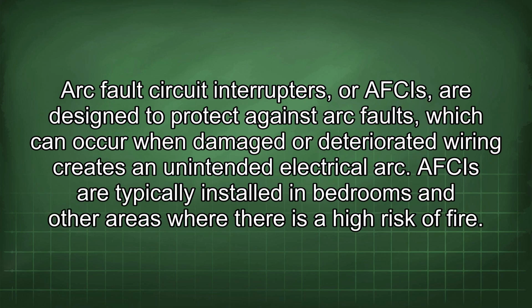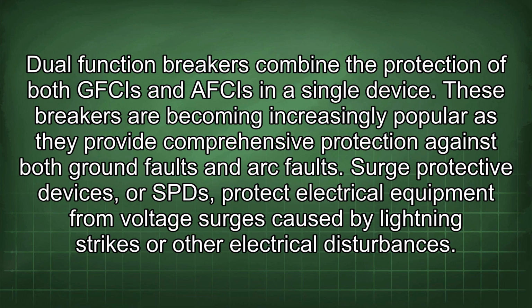Arc fault circuit interrupters, or AFCIs, are designed to protect against arc faults, which can occur when damaged or deteriorated wiring creates an unintended electrical arc. AFCIs are typically installed in bedrooms and other areas where there is a high risk of fire. Dual-function breakers combine the protection of both GFCIs and AFCIs in a single device. These breakers are becoming increasingly popular as they provide comprehensive protection against both ground faults and arc faults.